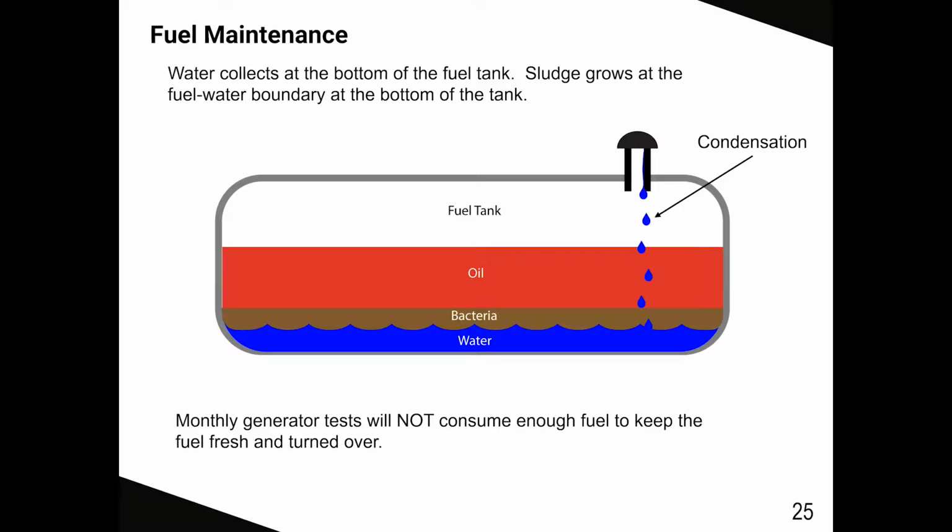Generators have a 10 micron filter that will clog and shut the generator down in the middle of the blackout. The solution is a fuel oil maintenance system. These both dewater the fuel and oil and filter down to 5 microns. We recommend a dedicated supply and return pipe on the opposite ends of the tank to ensure fuel oil turnover.